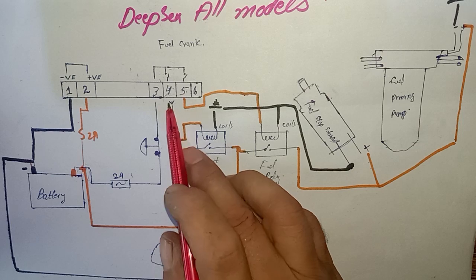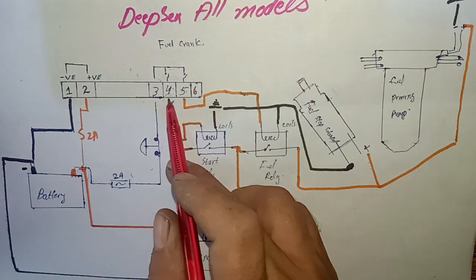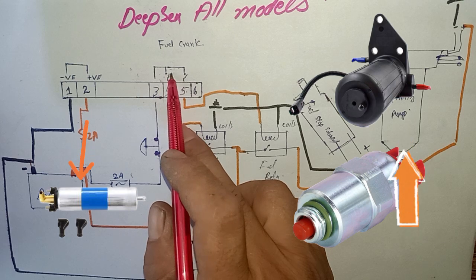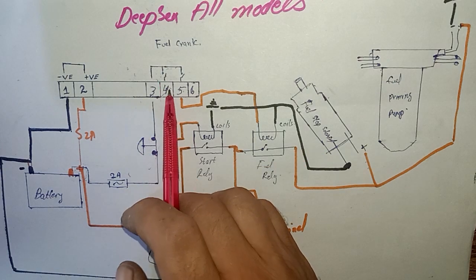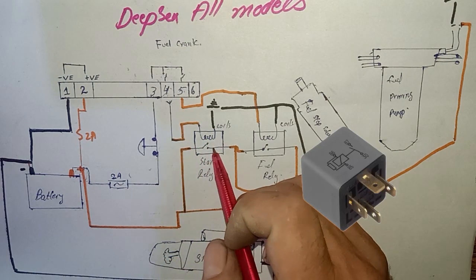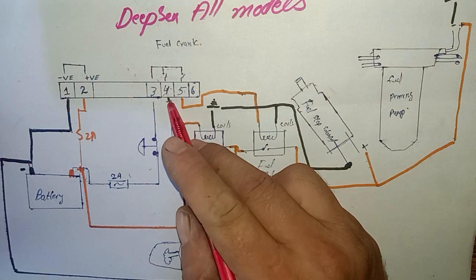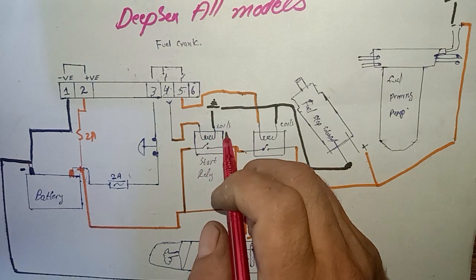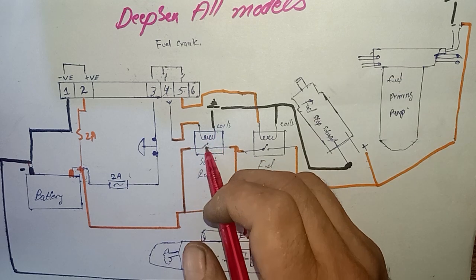As you can see here, when we press the green button of the Deep Sea controller, the controller closes the switches for fuel turn-on and for starter motor turn-on. When this switch is closed, it sends a positive feed to the relay coils. The starter relay has one side as the signal from the controller and one side grounded. The relay coil has two points — one negative and one positive — and also NO and NC contacts. This relay is normally open.